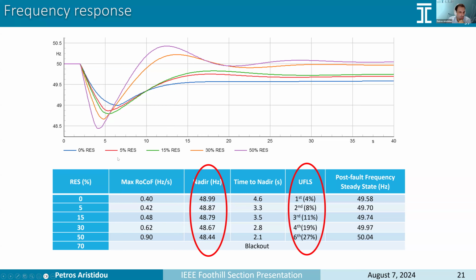We can see that even with 0% renewables, we have a nadir of less than 49 hertz. And when we go to 50% renewables, it goes down to 48.44 hertz. The only reason that the system survives is due to the under-frequency load shedding scheme, where in the case of 50% renewable penetration, it goes to the 6th stage of under-frequency load shedding, which means that 27% of our consumers have been disconnected in order for the system to survive.